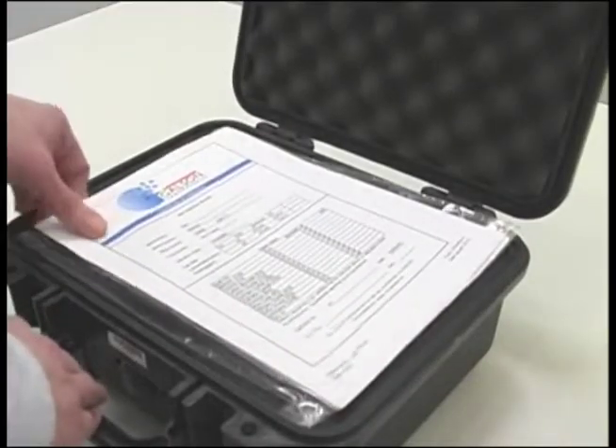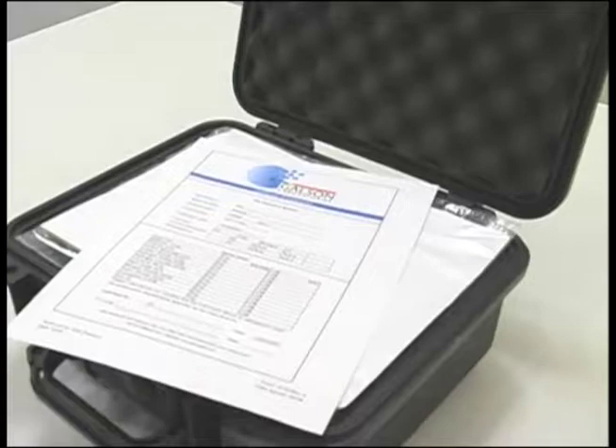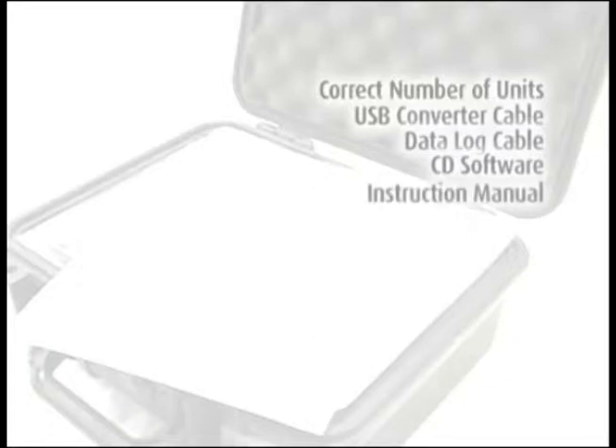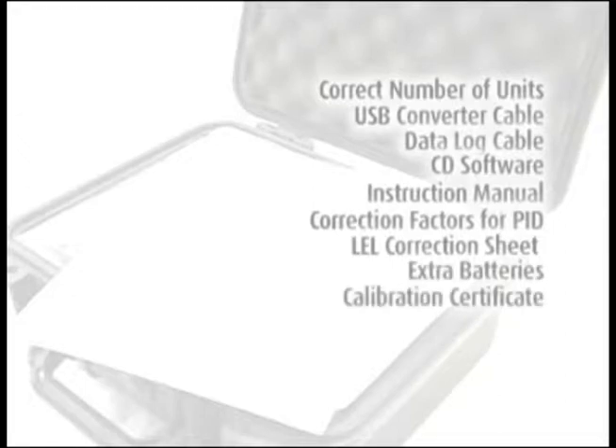When you first receive the shipment of your MultiRAE gas monitor, confirm you have received everything you ordered. You should have the correct number of units you ordered, USB converter cable, data log cable, software CD ProRAE Suite, instruction manual, technical note 106 correction factors for PID, an LEL correction sheet if you requested LEL as part of your setup, extra batteries, calibration certificate, and water vapor filter trap.